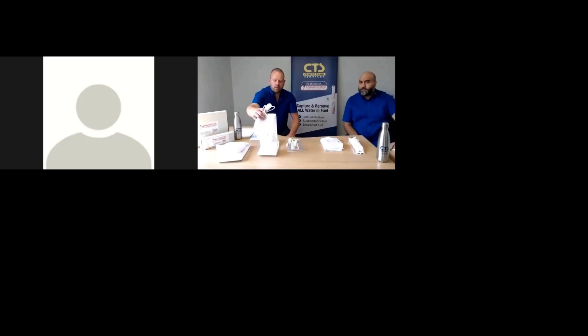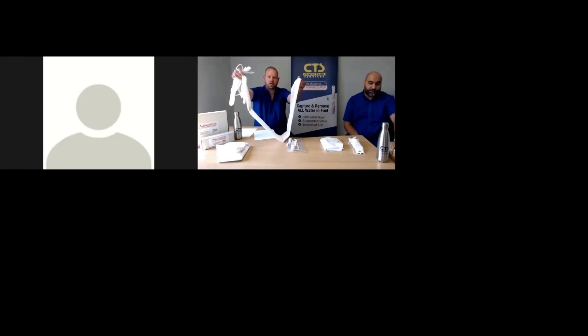The next one is for our main static storage tank. This is ideal for your plastic storage tanks — this is the anaconda. It will go into a tank up to 2,500 litres. It's got weights inside of it and it'll go through a 9 centimetre opening. Some of the smaller 2,500 litre plastic tanks from the popular manufacturers — you can put it through the inspection hatch, tie it off, leave it suspended in the fuel or drop it to the very bottom, depending on how you're going to install it. Perfect for the agricultural environment and smaller 2,500 litre tanks.